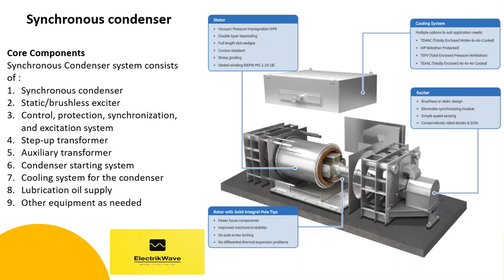Core components: A synchronous condenser system consists of the synchronous condenser, static or brushless exciter, control, protection, synchronization and excitation system, step-up transformer, auxiliary transformer, condenser starting system, cooling system for the condenser, lubrication oil supply, and other equipment as needed.